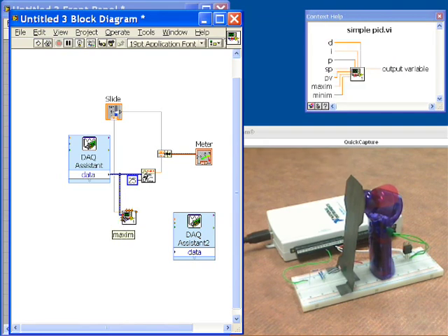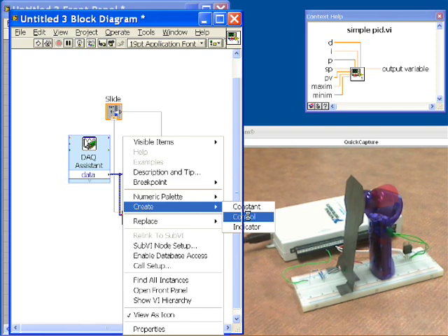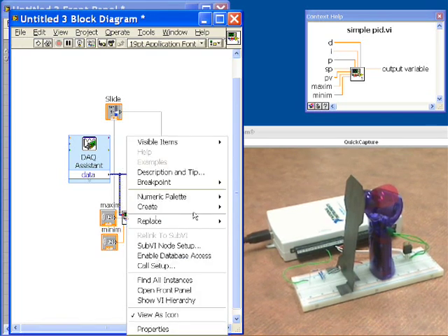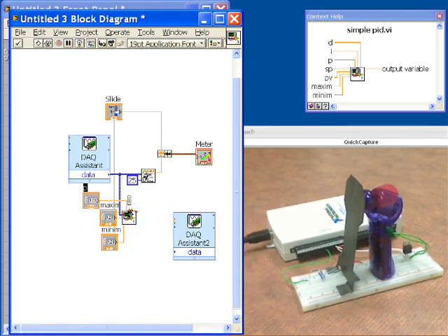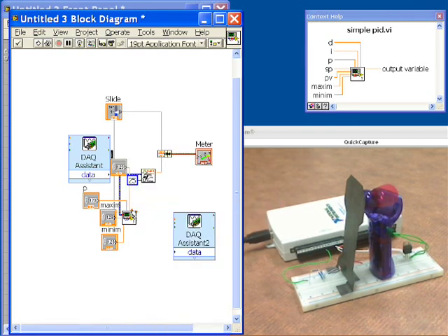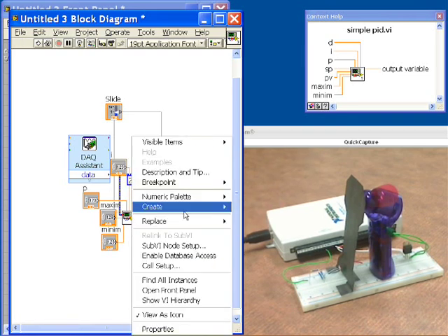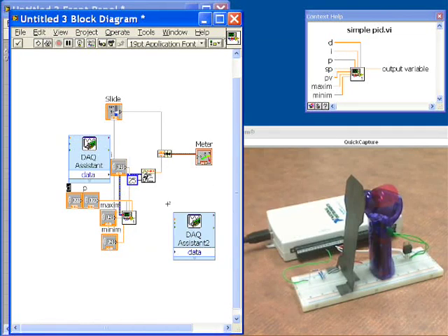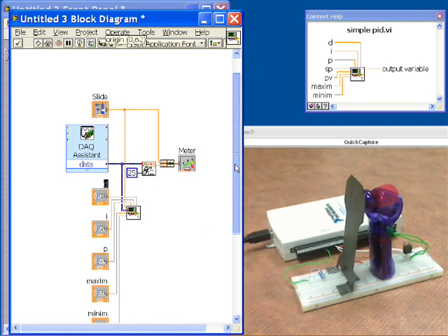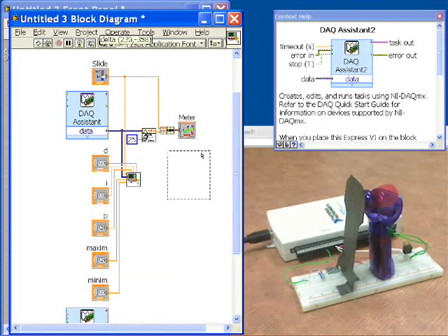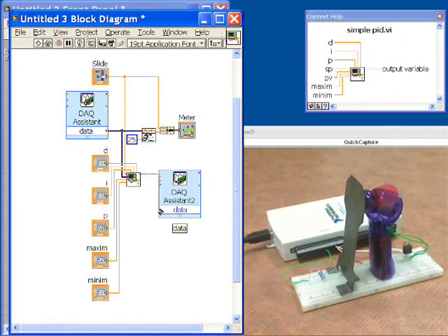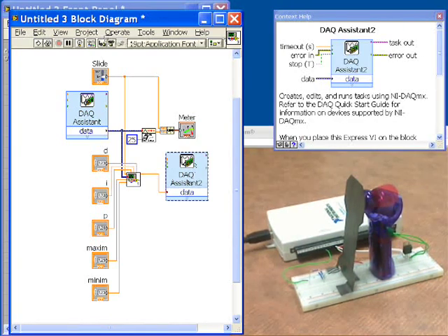The other thing that we'll do is create controls now that we can set from the front panel for all of the other variables that go into PID. So things that we can set there are the minimum values and the maximum values. And that just limits what the min and max output of the PID can be. And then we'll create variables for the P, the I, and the D coefficients that we'll be able to change from the front panel as well. So that sets everything up. It's nice and clean now. And finally we would like to take the output of the PID and wire that up to the real world output of the analog output. So we'll wire that in and that's set and ready to go.